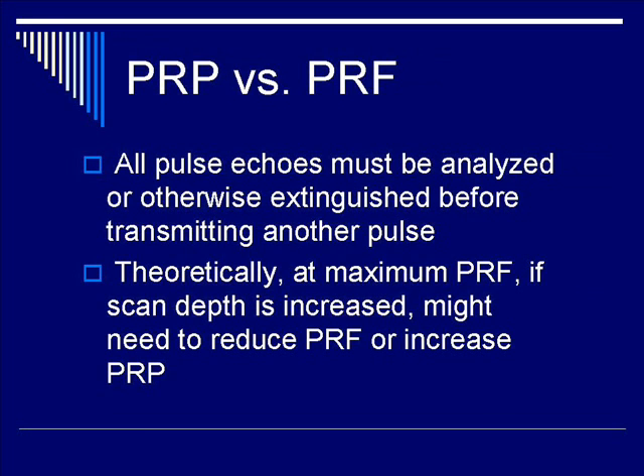In summary, all pulse echoes must be analyzed or extinguished from the first pulse before transmission of a subsequent pulse. Theoretically, at maximum PRF, if the scan depth is increased, you would want to reduce the PRF or increase the PRP so that you don't get multiple echoes.